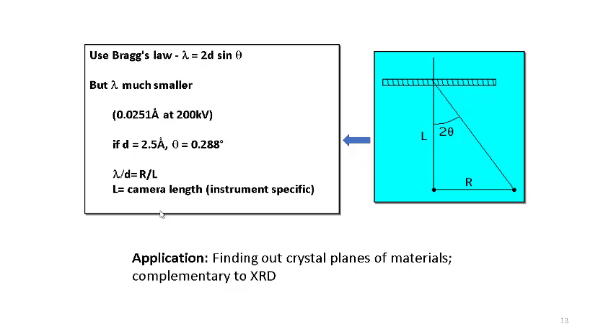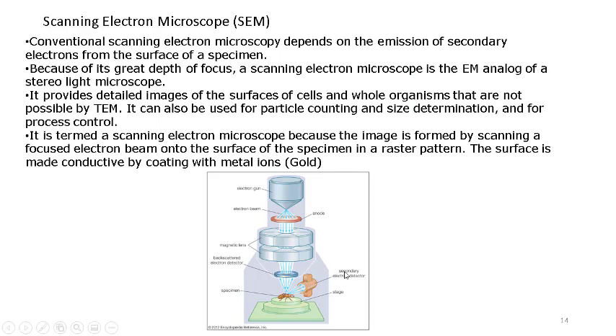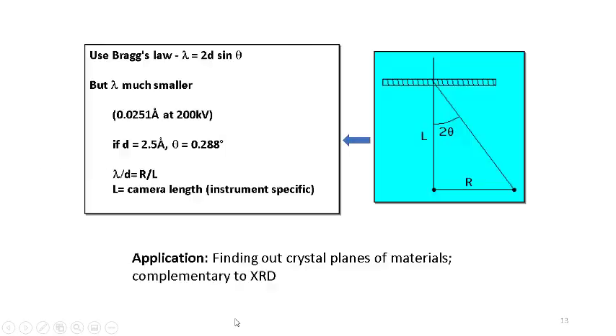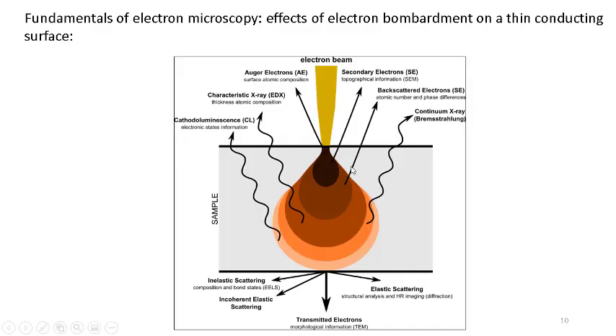Scanning Electron Microscopy (SEM) depends on the emission of secondary electrons from the surface of the specimen. Secondary electrons come from a shallow depth of the sample and provide information analogous to a stereo light microscope. In a stereo light microscope we find features in the micron or millimeter order, whereas in SEM we find features in the nanometer region. The material must be conductive for SEM; non-conductive materials like polymers are dried and coated with metal ions such as gold.